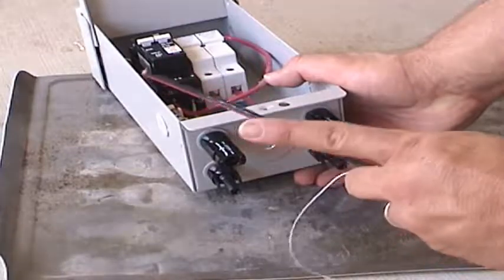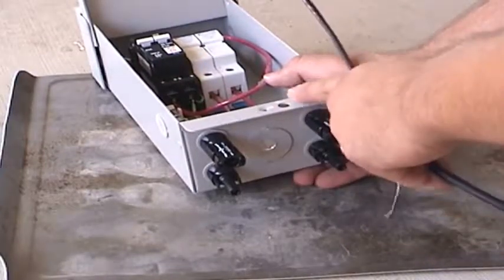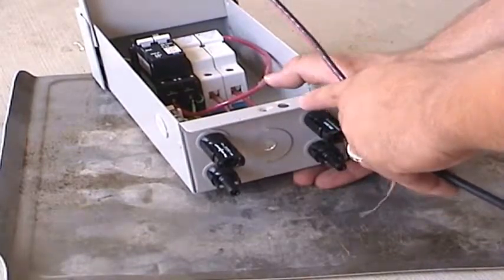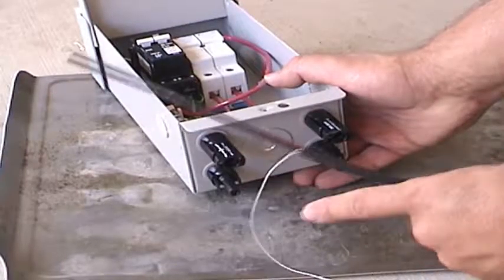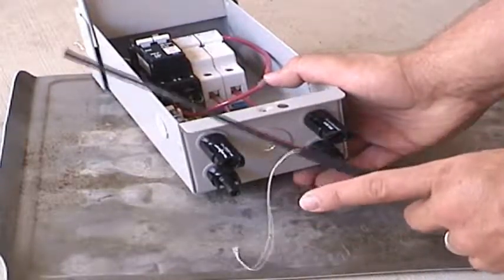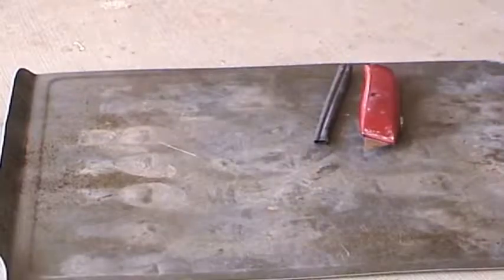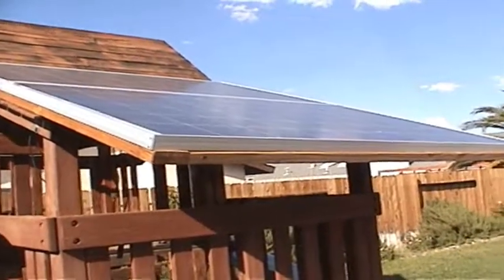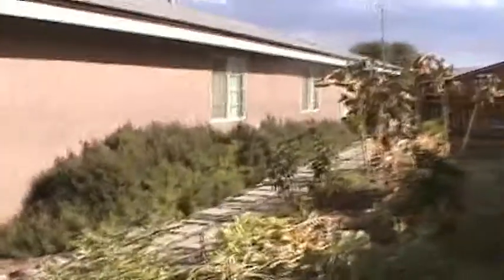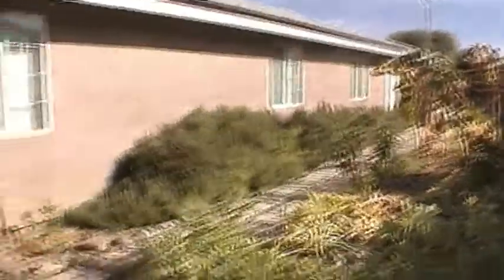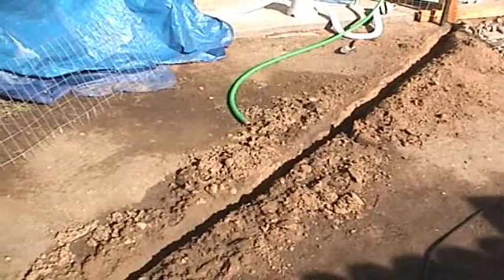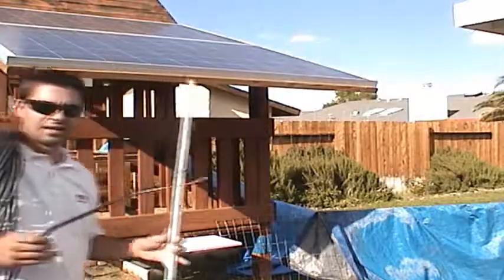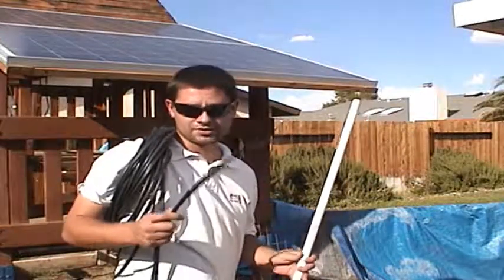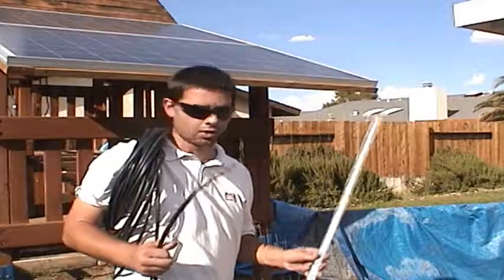Now before we actually feed the cable into the combiner box and wire it up, let me show you one more thing that will save you some hassle later on. In order to get power from your solar panels to the battery bank in your garage, you'll probably need to run your outdoor cable underground for at least some distance. Now technically you can bury this outdoor cable directly underneath the ground.